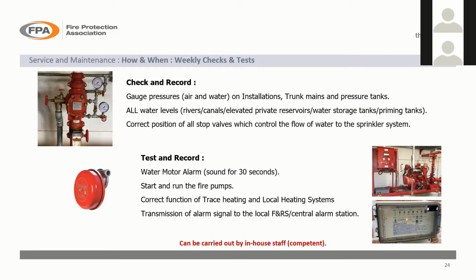Somebody would check the pressure gauges, the water levels, and the correct position of all the stop valves. They're just checks, and they should be recorded onto a weekly sheet. Then you need to test and record things like the alarm gong sounds of your valve set once a week, and then start and run your fire pumps. If you've got two fire pumps, you need to run both of those. You need to check the correct function of the trace heating systems, and importantly, check that the transmission of any alarms to any off-site local fire and rescue service or central alarm stations is also functioning correctly.